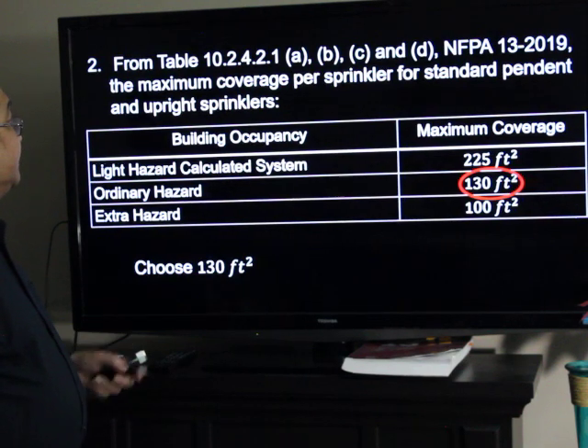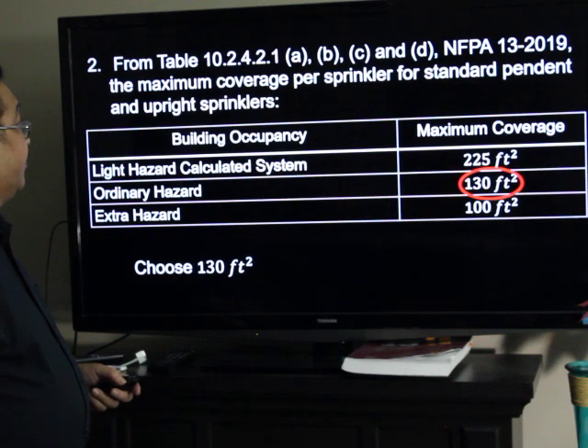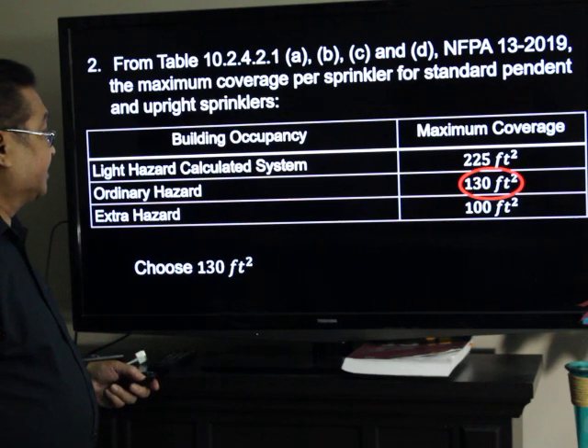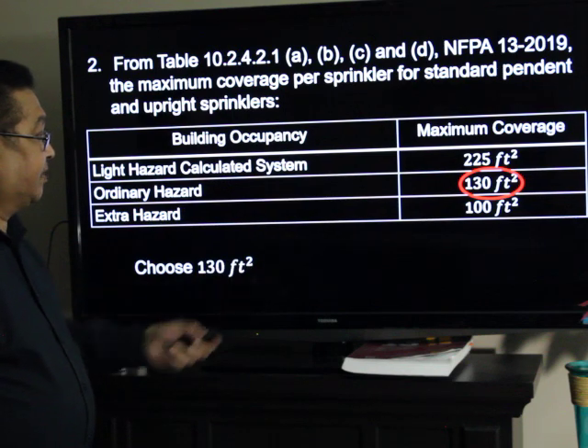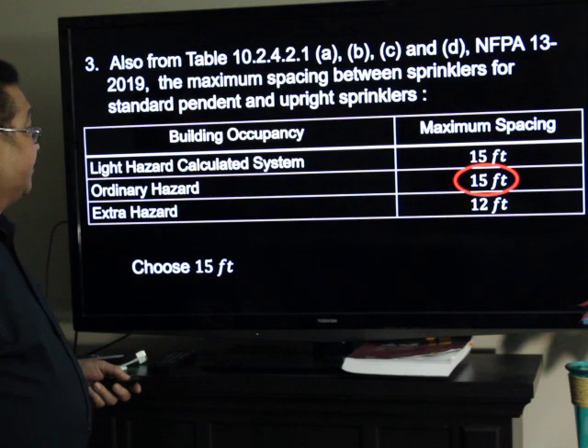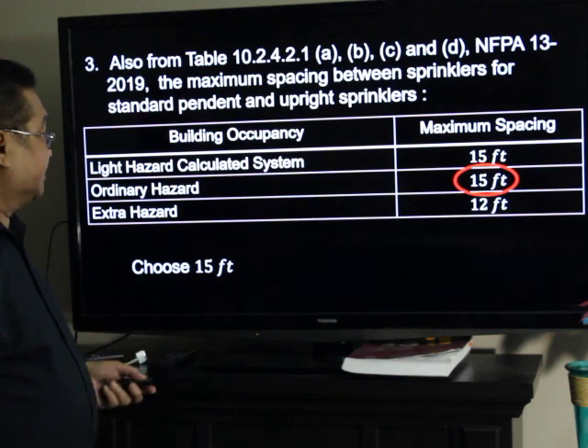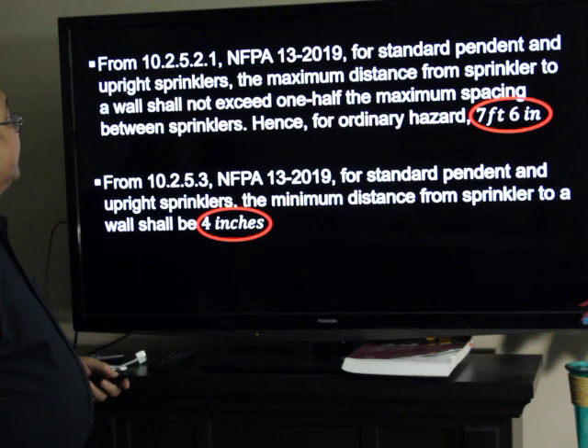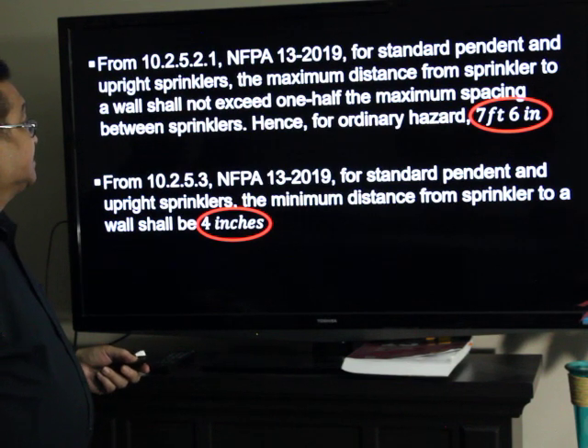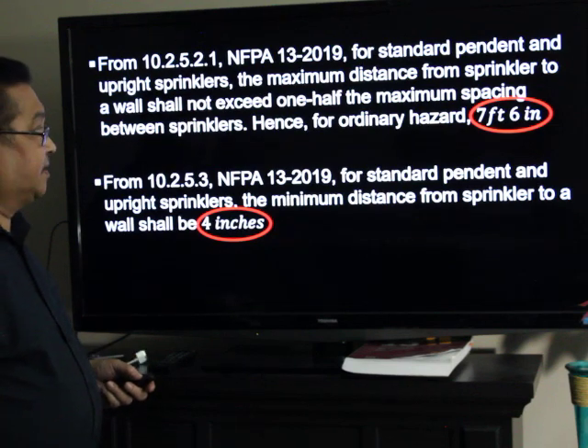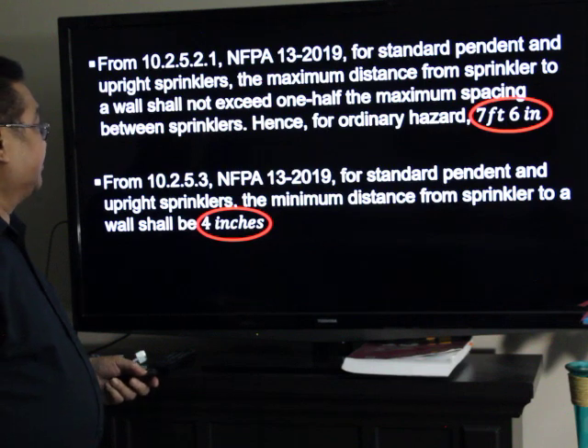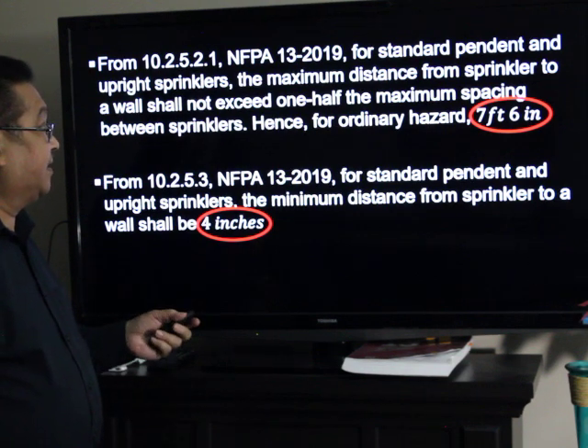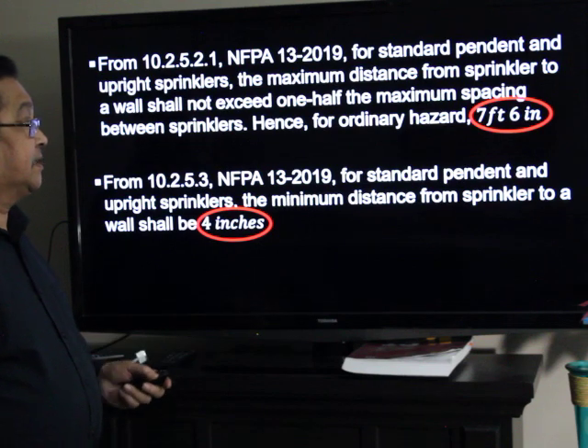And from the same standard, Table 10.2.4.2.1, for pendant and upright sprinklers, the maximum coverage for Ordinary Hazard classification is 130 square feet — see the one encircled in red. From the same table, the maximum spacing for these sprinklers, for the same building occupancy classification, is 15 feet. The standard also says that the maximum distance from the sprinkler to the wall shall not exceed one-half of the maximum spacing between sprinklers. Hence, since we choose 15 feet as spacing maximum, the maximum distance from the sprinkler to the wall is 7 feet and 6 inches.